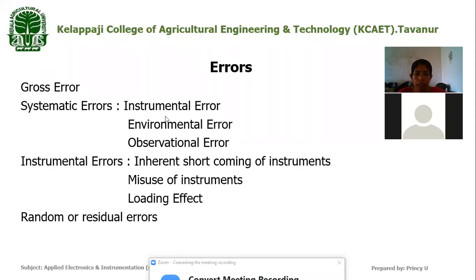It is inherent in that instrument. Inherent means at the manufacturing time itself, there will be some error present in that meter. And how can we eliminate it? By calibrating against a standard, and a correction factor should be applied after determining the instrumental error, and the instrument may be recalibrated carefully. Okay, by doing this much, we can eliminate the instrumental error.